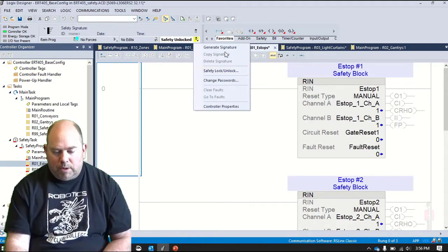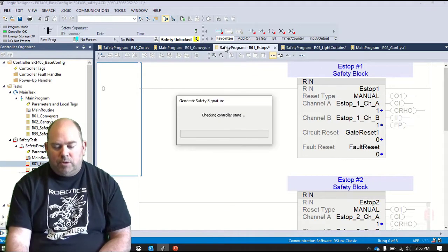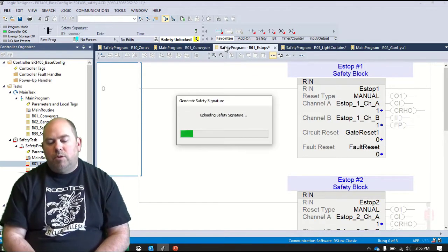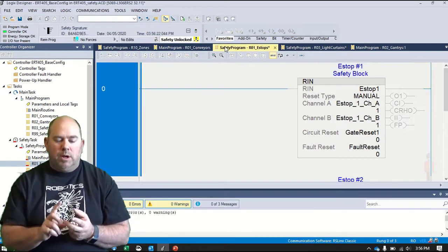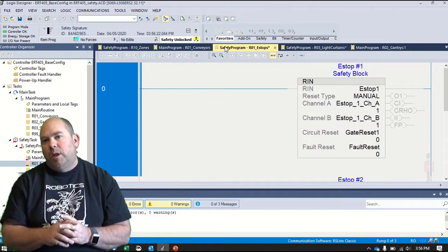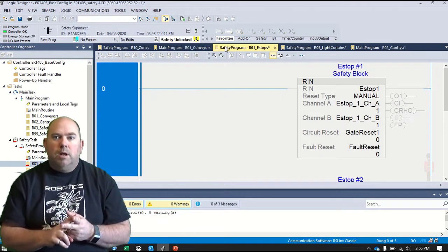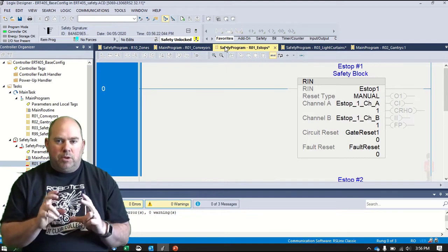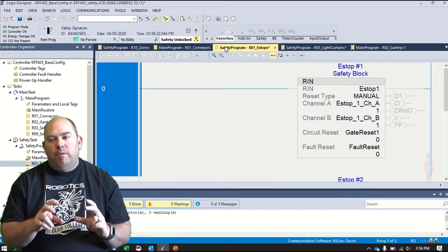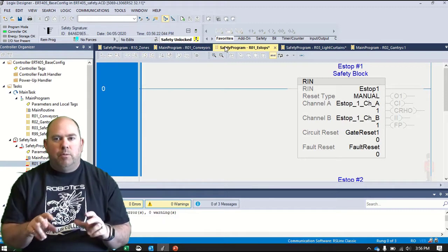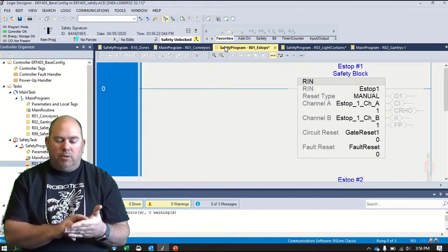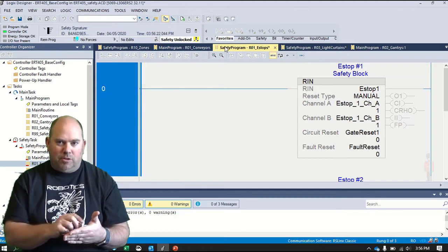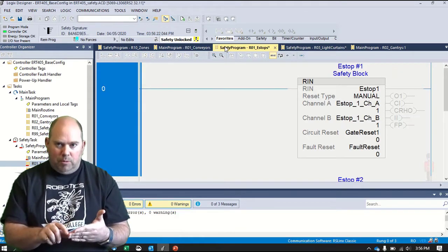First thing we're going to do, though, is generate the safety signature. So if I say generate the safety signature, what this is going to do, and we'll look at this in a second, this is actually going to create a code and a timestamp that goes with this. So you're going to record this safety signature, and this is basically your verification of this is the code when I left it. So when I validated the system and locked it, I created this safety signature. This is like you signing a document, and this is the code that was in there.